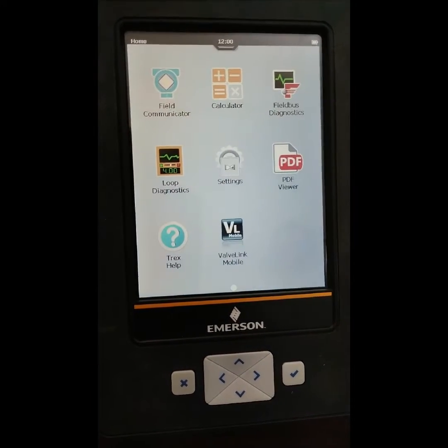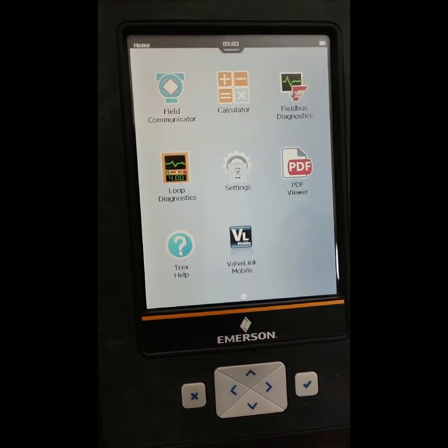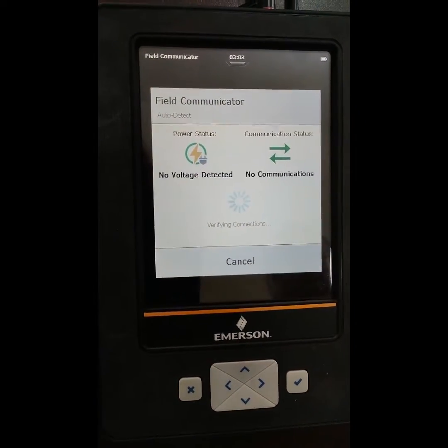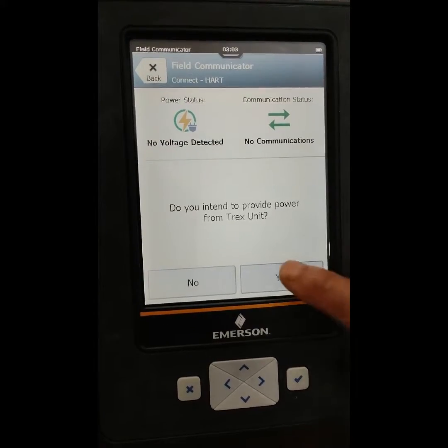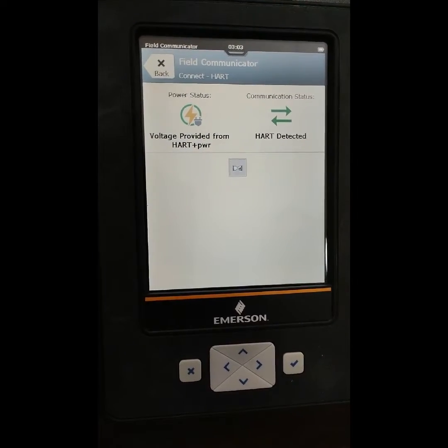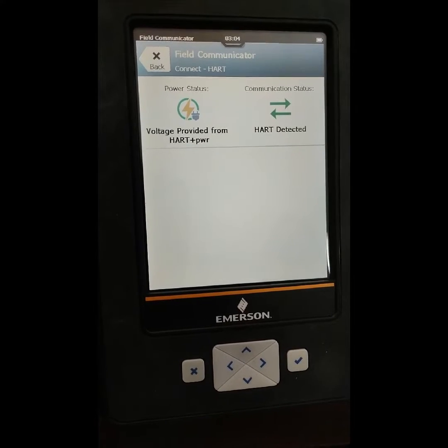Go to the field communicator and press it to open. The field communicator is now open. Here we select HART, then click on transmitter. There was a warning that we want to supply power from the Trex — we select this. There is transmitter and positioner; we select transmitter. Voltage provided from HART plus power terminal is detected, HART is also detected, and power is supplied from the Trex to the transmitter.